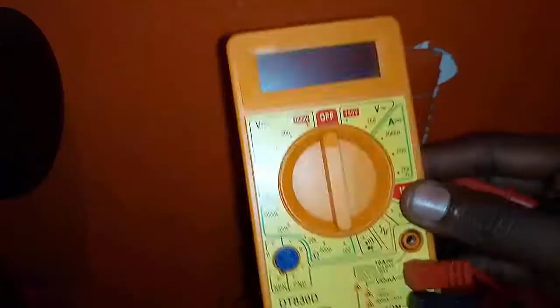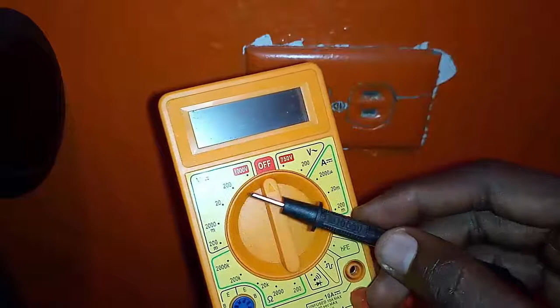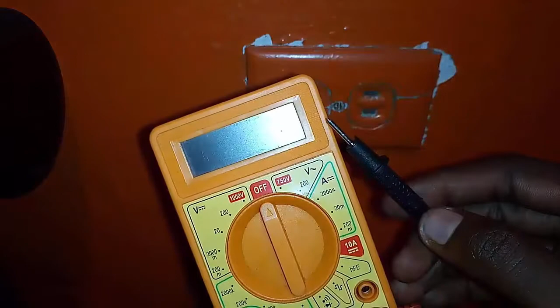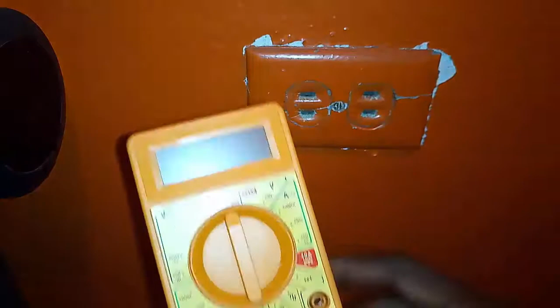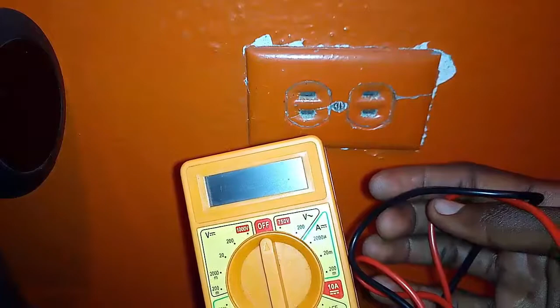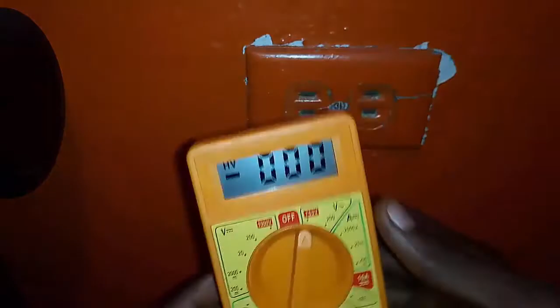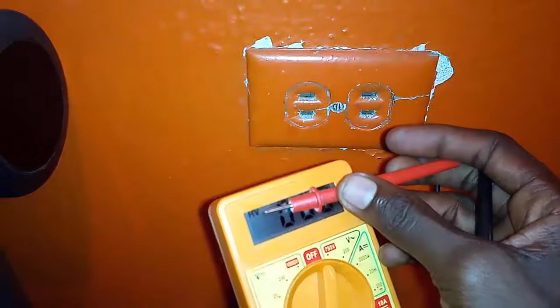Okay guys, so we move to an outlet. Let me make it easy to understand. If you are about to test for 19 volt or 20 volt, you have to put it above 20 volt, and if you are about to test for 200 volt, you have to put it above 200, that is about 500 volt. So we understand in Africa the normal current we use here is 240 volt, above 220, so we cannot put the tester on 200 or else it's going to cause problems for us. So we are going to put it on 750. As you can see, when we put it on 750, we have half voltage.